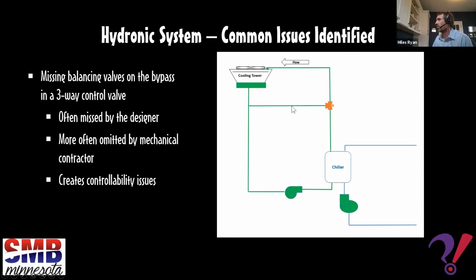You don't want this to be no balancing valve, because then you're going to short circuit water there. It's going to become very unstable, and this valve is going to start hunting. The moment this valve starts to try to control for temperature, very rarely do you see this done well if there's not a balancing valve there. It's just a controllability issue.